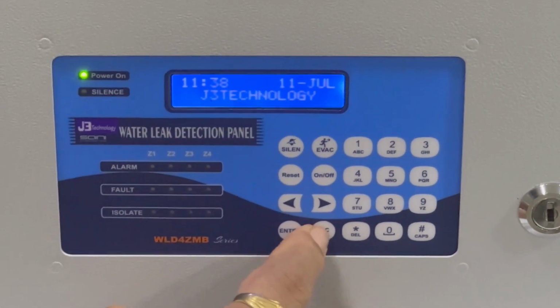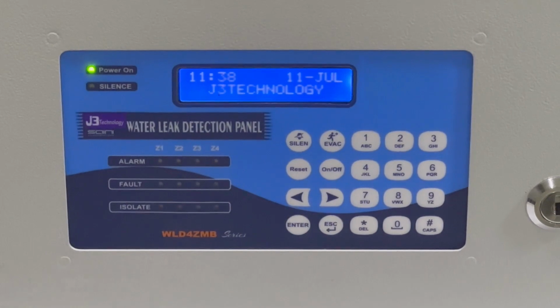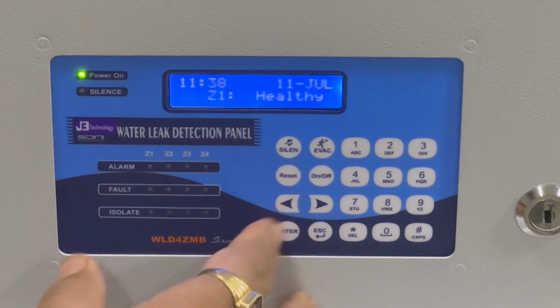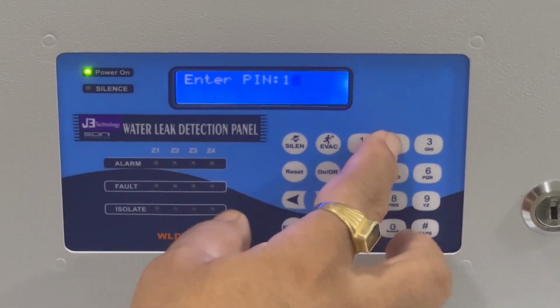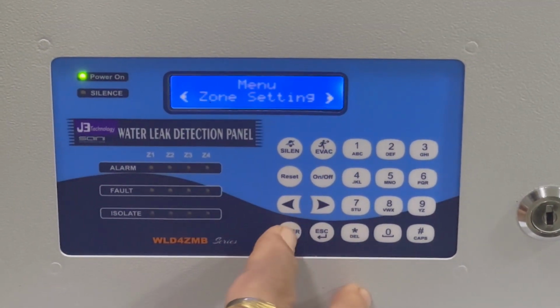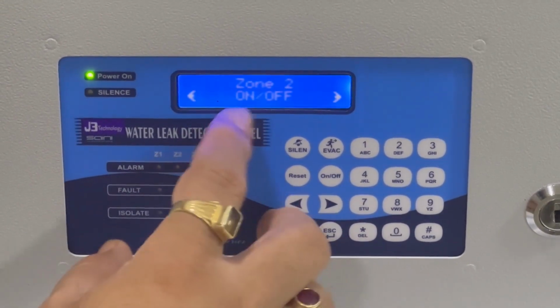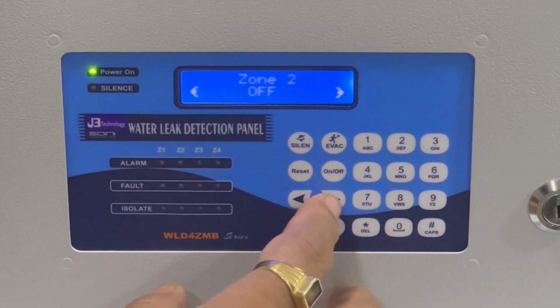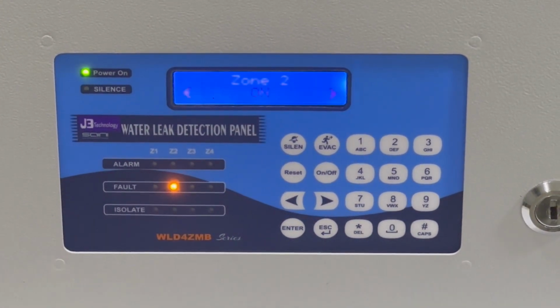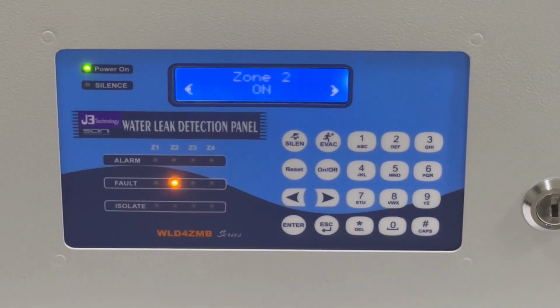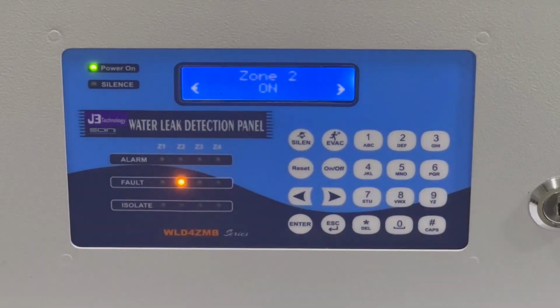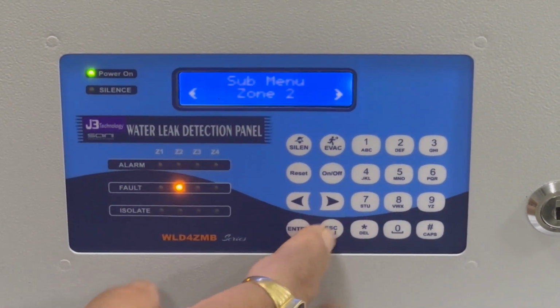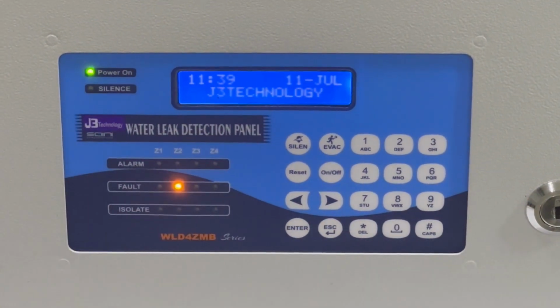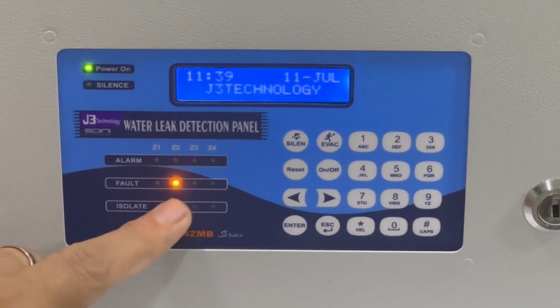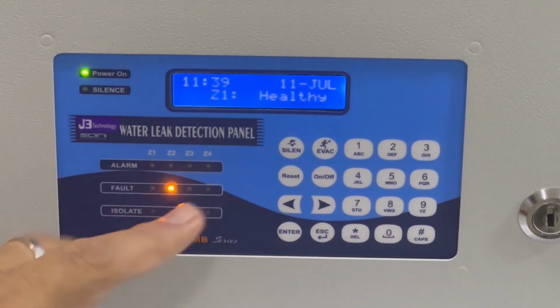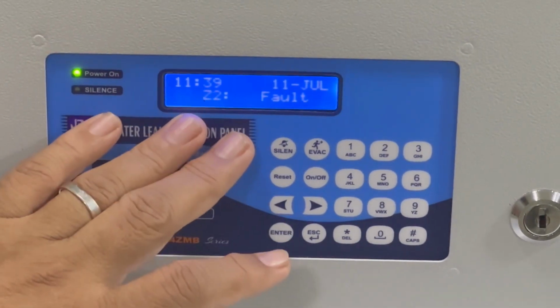Now I can show you. In fault mode, the panel will beep for 5 seconds and then automatically silence. For example, I will turn on the second zone, which we are now using. Zone setting, zone second. I turn on that feature, and the panel will go into fault condition. See, the panel gets silenced. Within 5 seconds, the panel has a fault, but the internal buzzer gets silenced, because I have kept the auto silence feature on for fault condition. In this case, the panel will automatically silence in fault condition with whatever time you have defined in the auto silence mode.